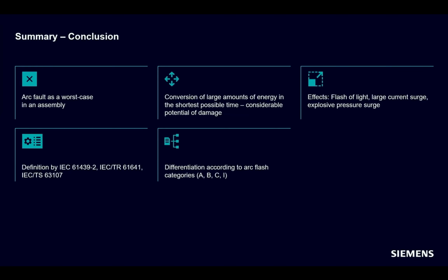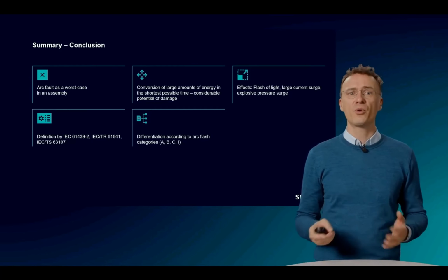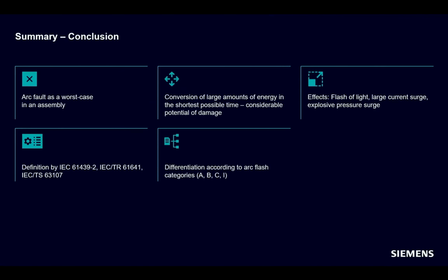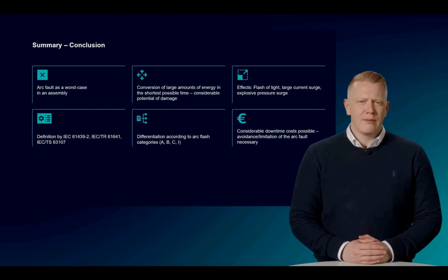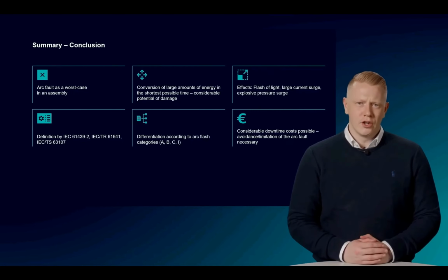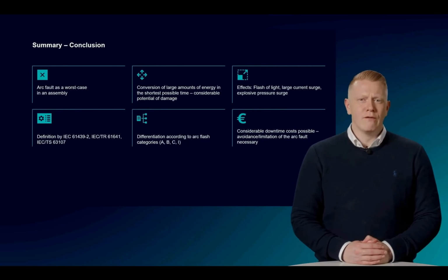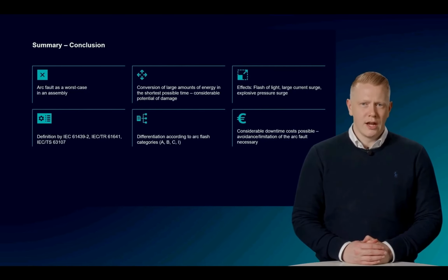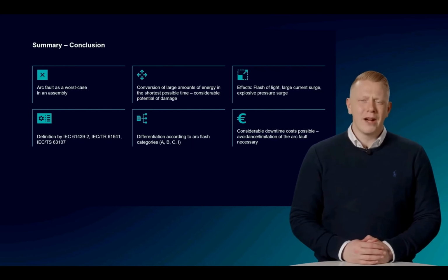A distinction is made between arcing class A, personal protection, class B, personal protection and assembly protection, and class C, personal protection and specific assembly protection, including emergency operation after an incident. An arc fault is inevitably accompanied by an outage of the system as well as downstream processes. The resulting downtime costs can quickly reach a financially sensitive area, leading to further additional costs. Therefore, it is important to avoid arc faults and their consequential costs, or to minimize them as much as possible.